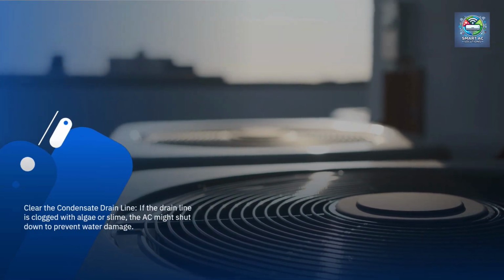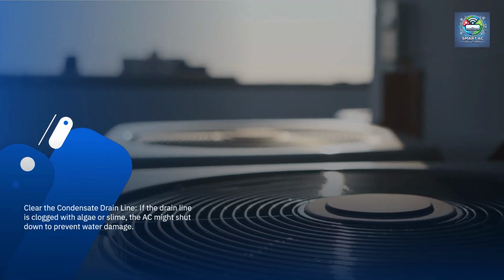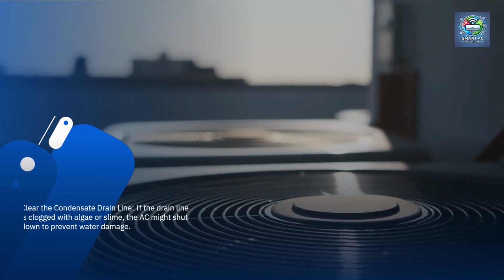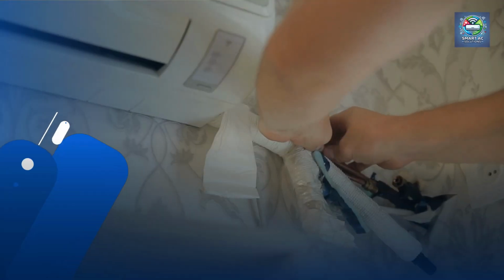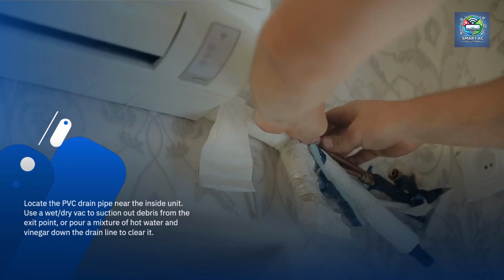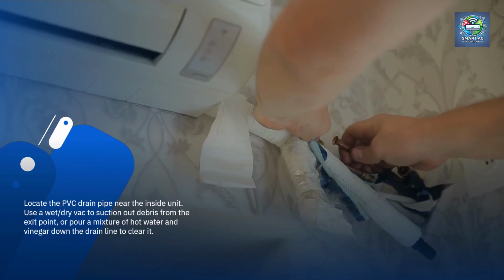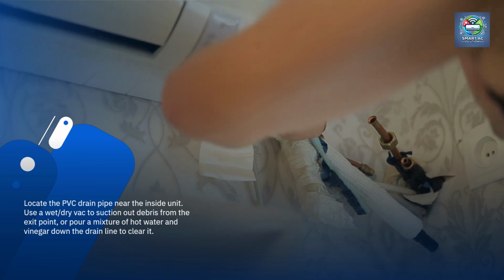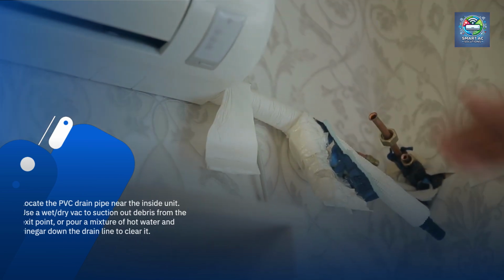Clear the condensate drain line. If the drain line is clogged with algae or slime, the AC might shut down to prevent water damage. Locate the PVC drain pipe near the inside unit. Use a wet/dry vac to suction out debris from the exit point, or pour a mixture of hot water and vinegar down the drain line to clear it.